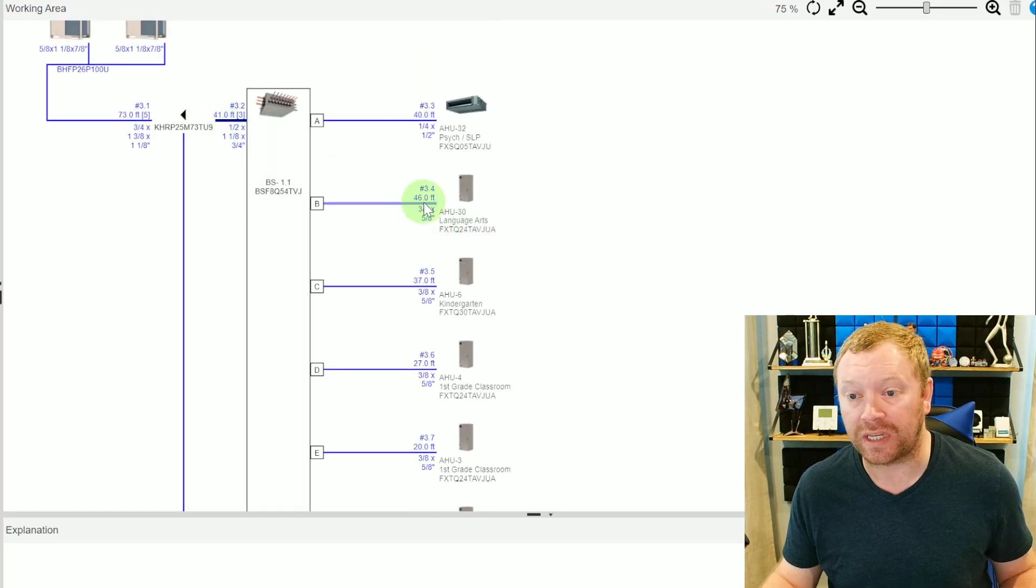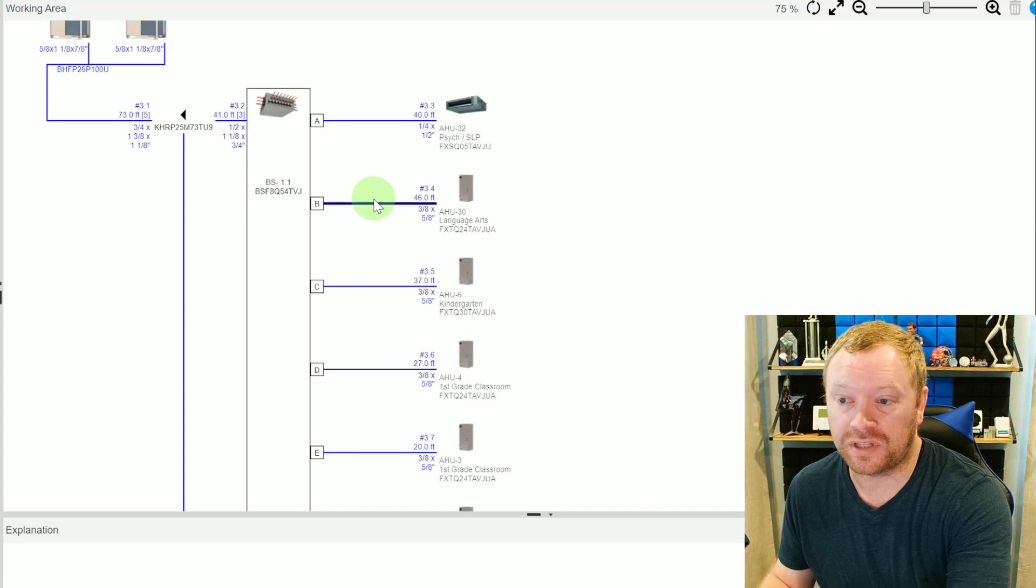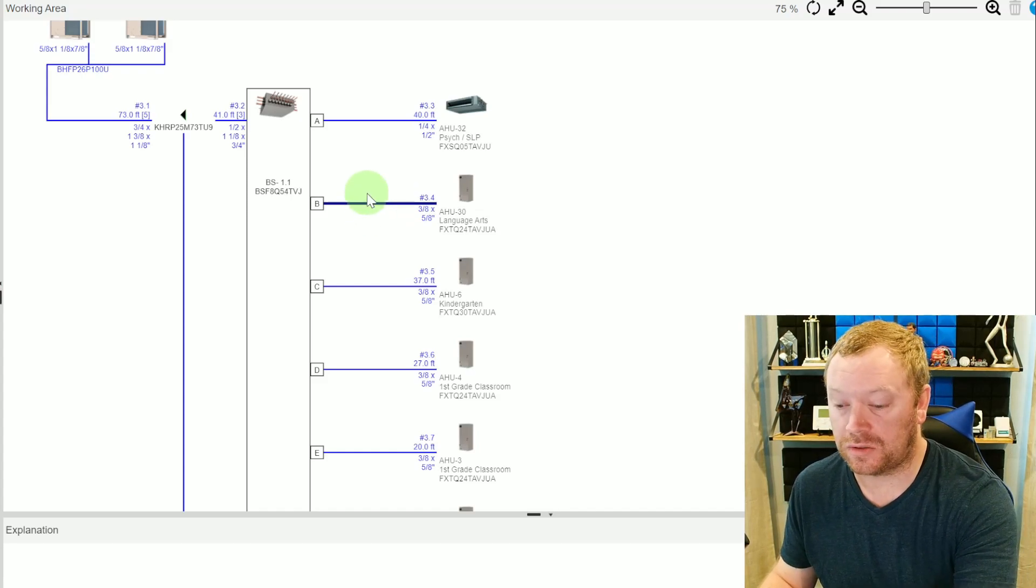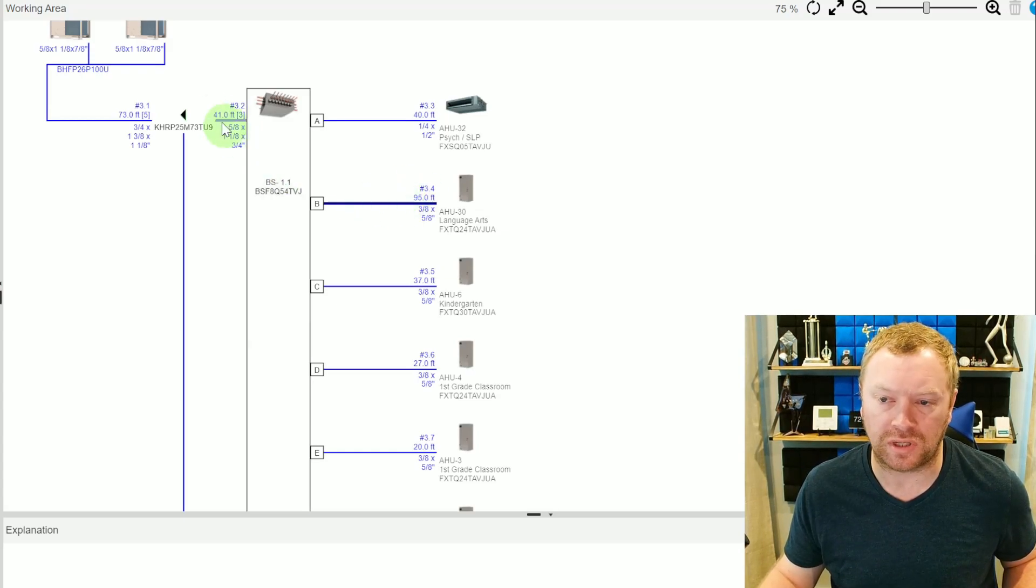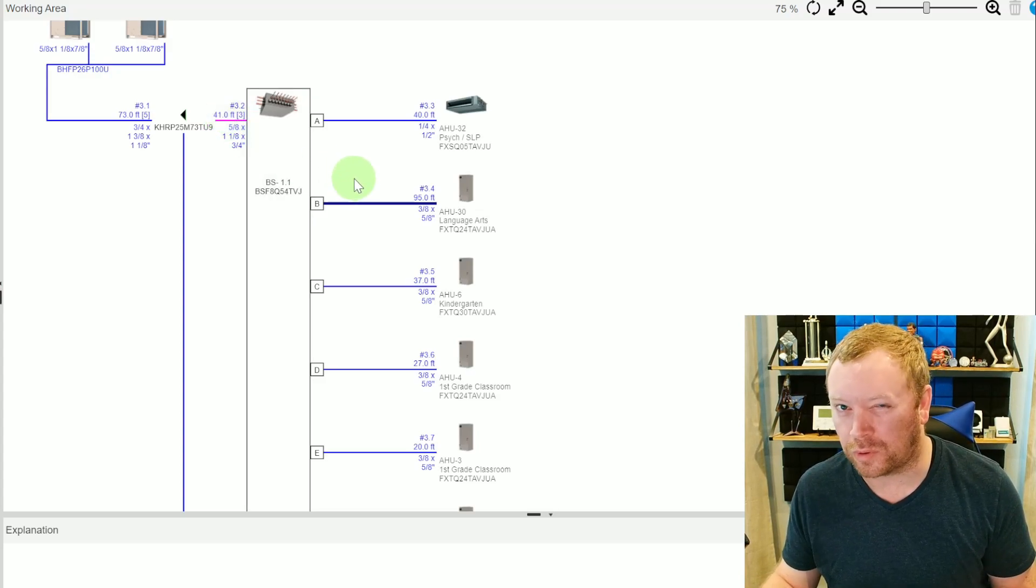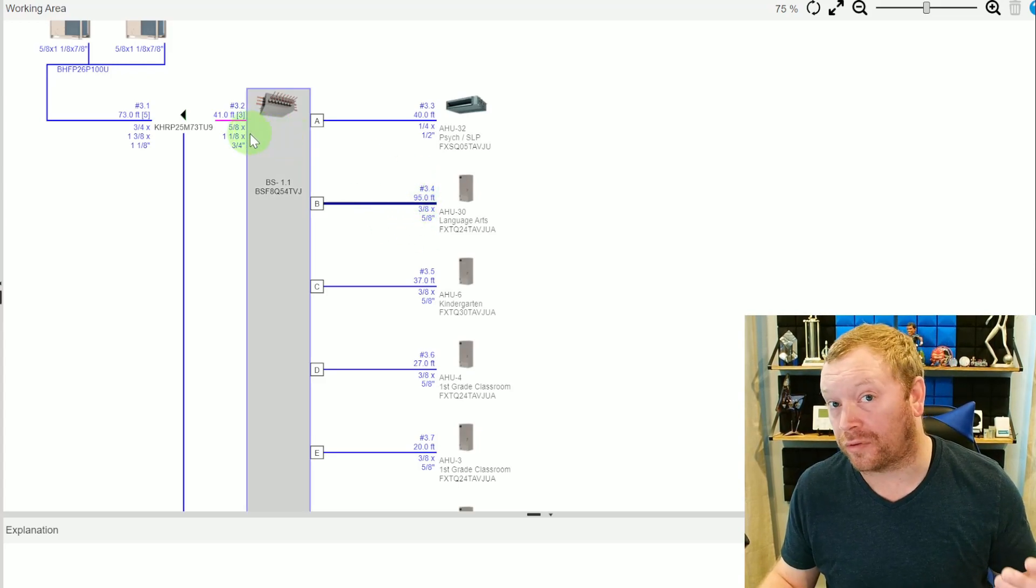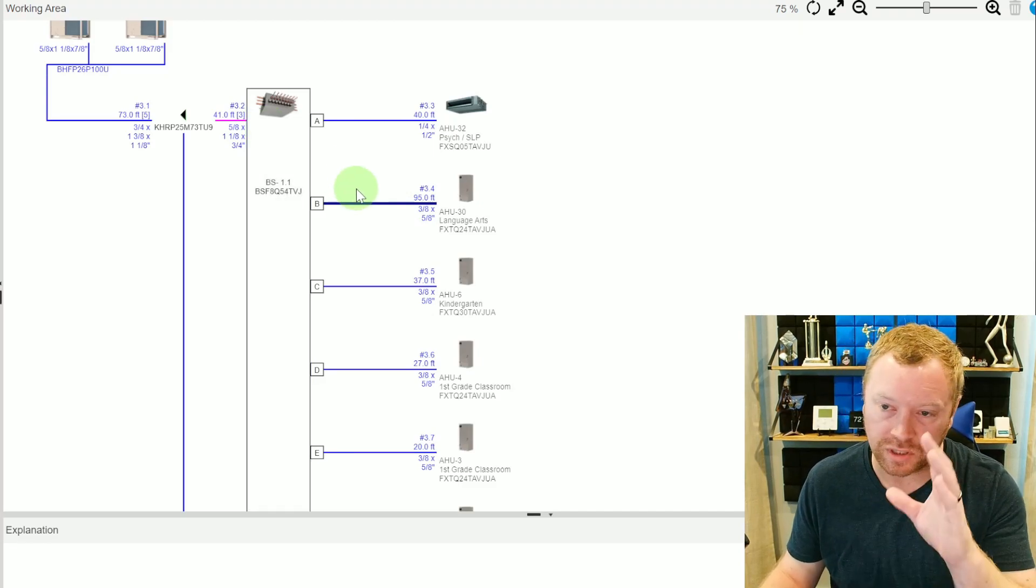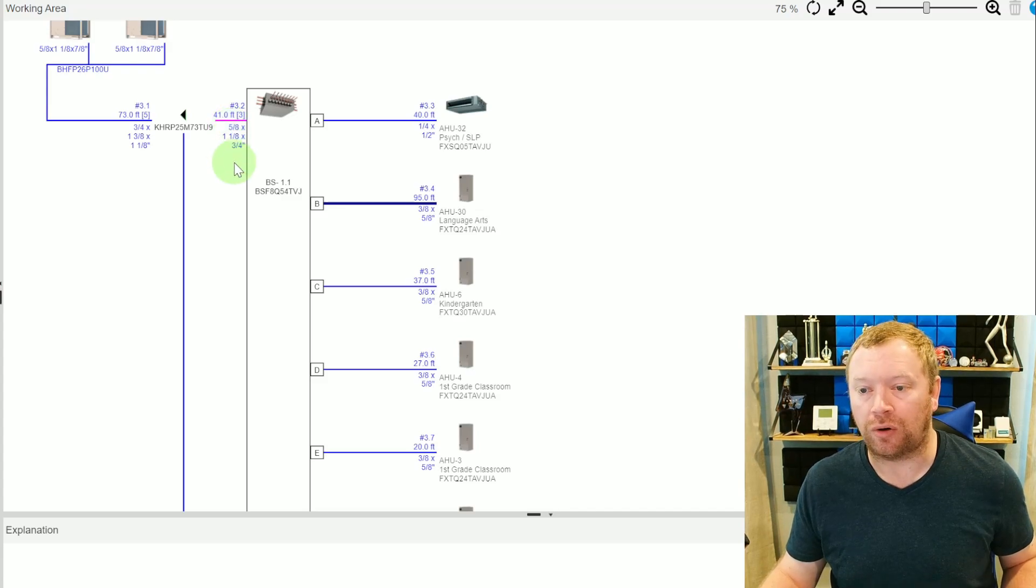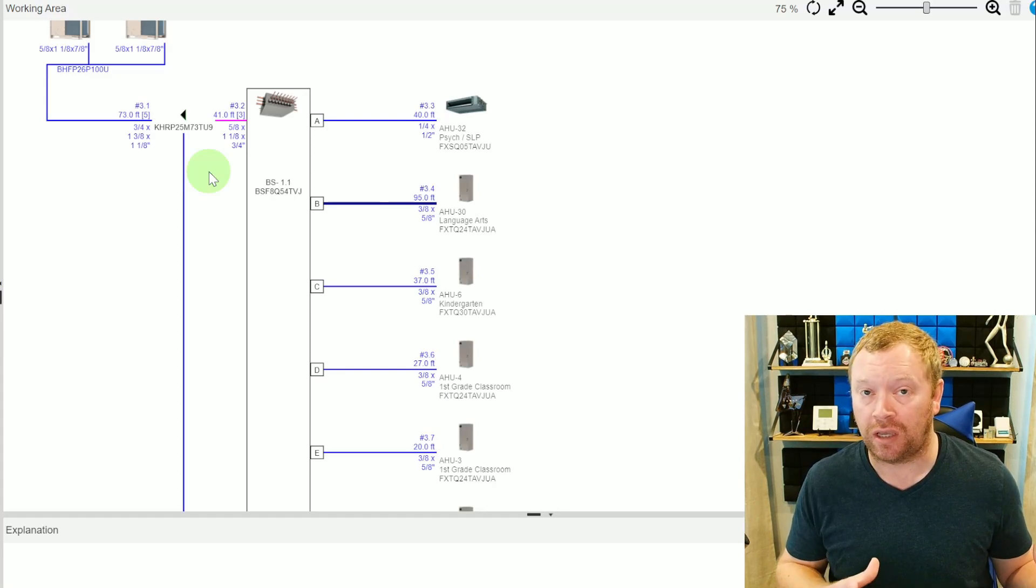So you'll notice that our longest run here is air handler 30. So 41 and 46 is 87 feet. So let's just change this and let's say that it was, I don't know, let's say it was 90 feet. Let's see that. No, not quite. Say this was 95 feet. You're going to notice that 95 feet plus 41 feet exceeds 130 feet. The technical is 131.2 feet, if you want to get really technical. That's why when I changed it to 90, 90 plus 41 was 131, which was less than 131.2. So now we just pushed it over and you notice that this pipe size changed.